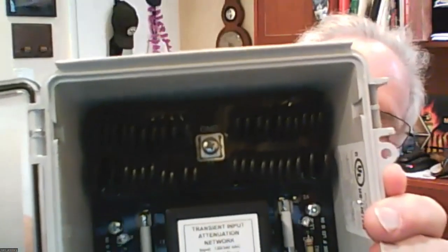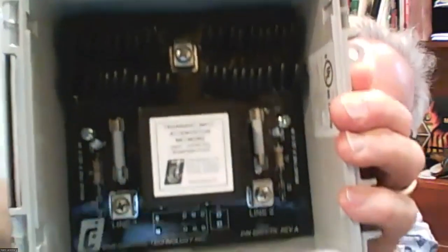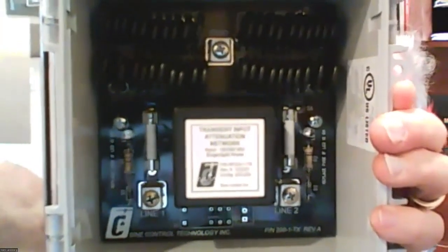is the secret sauce. If we open one of these up and take a look, I think you can see this. If you look at the top, you might be able to see it. You'll see a bunch of MOVs up there. Those are the things that take care of the very high voltage spikes caused by lightning. And then on the bottom, you see that thing with the square white label. That is the secondary low voltage suppressor, and it responds primarily to longer duration disturbances. A lightning spike of a couple of microseconds, it won't even see it.